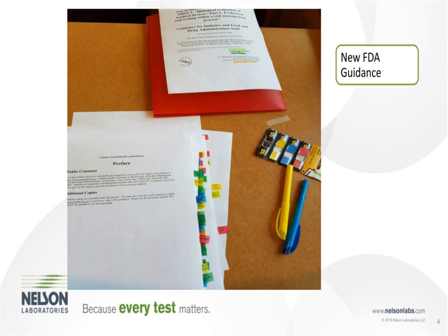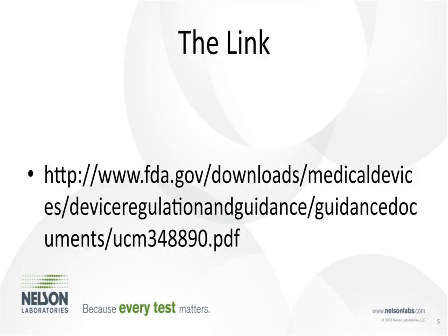What we have to do is identify that risk, evaluate to see what gaps are there, and then do a risk-benefit ratio. Does the benefit of the device outweigh whatever risks are associated with the device? That's what this whole biological program entails. When you develop a BEP, you fill in gaps with testing, and then you sum up with a biological evaluation report. You're really taking that holistic view of biocompatibility into account. And that's what the new age of biocompatibility is going to be.